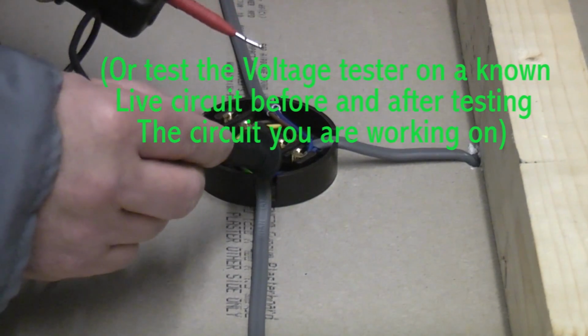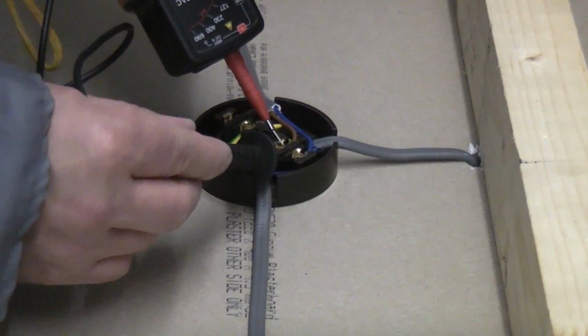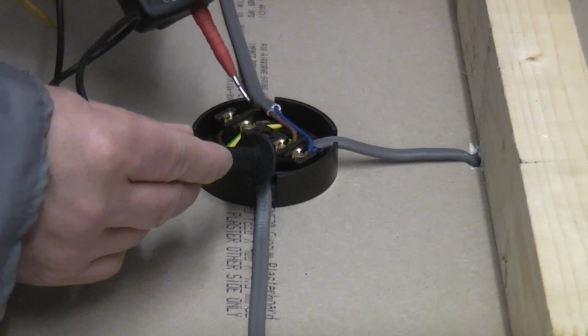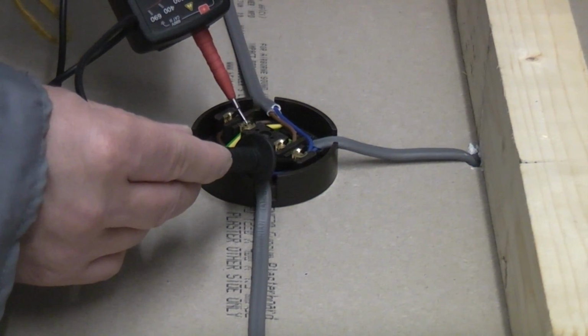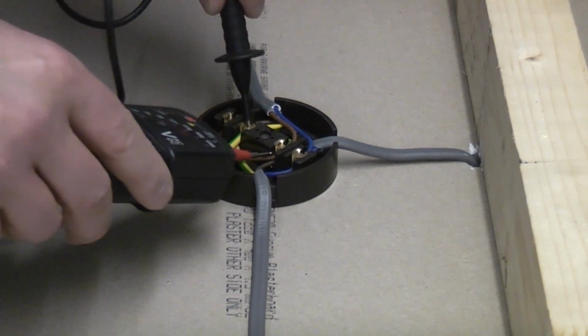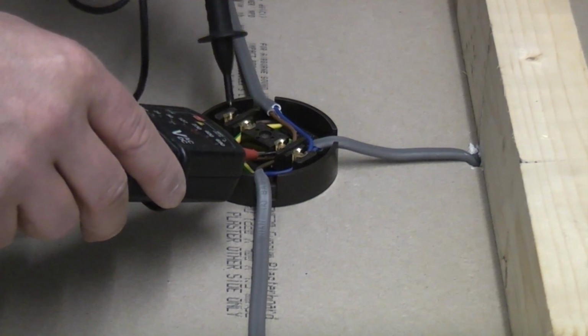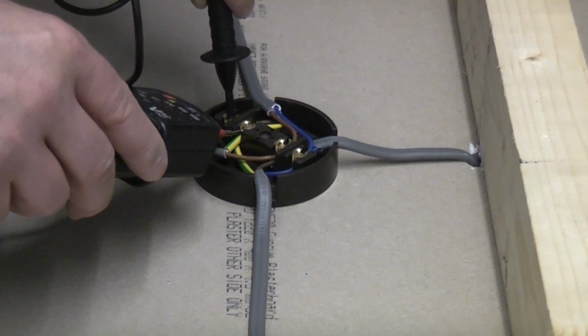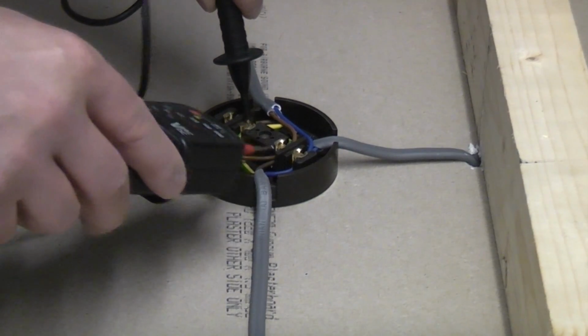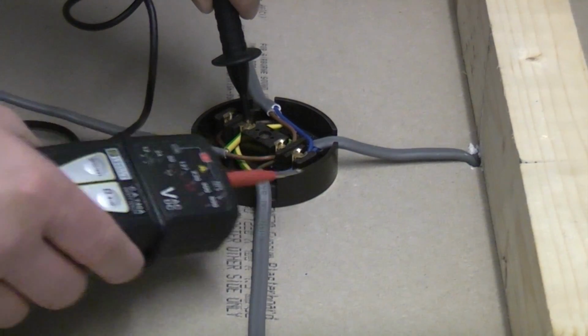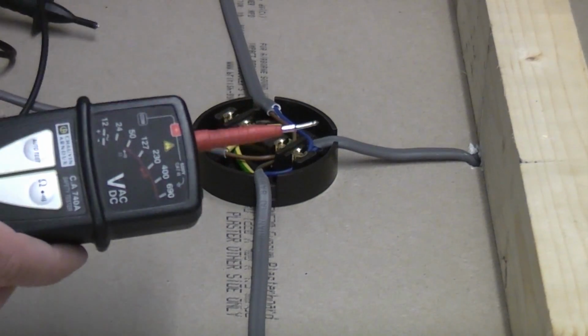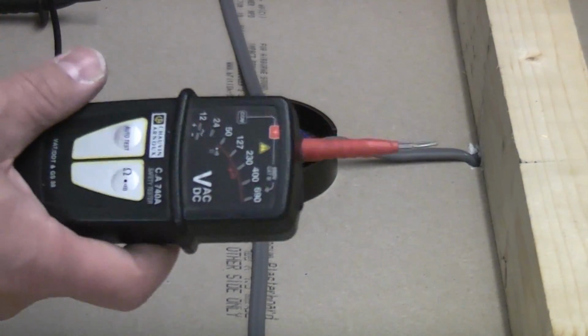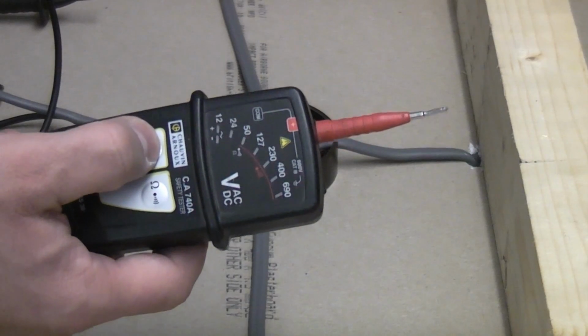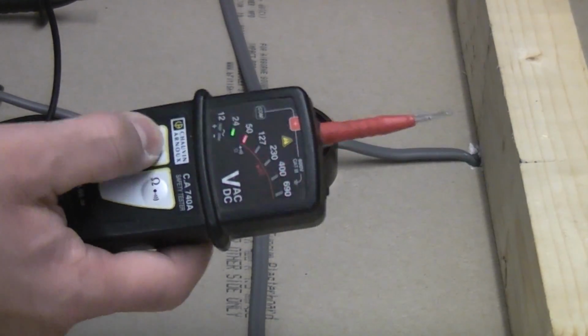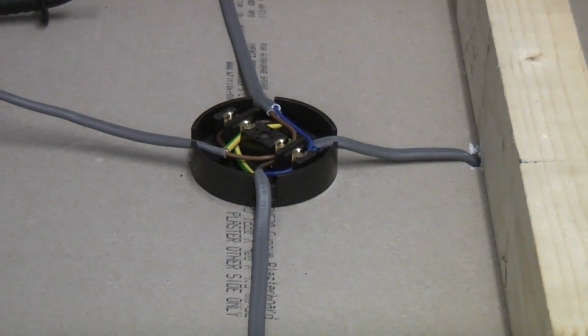We're now going to probe between neutral and live, which is dead, neutral and earth and live. And we'll also just check the switch live terminal. We can probe all of those terminals and the tester isn't lighting up at all, so it is completely dead. We are now safe to work on this circuit. Before we do, we need to check that the tester is still working, which it is. So we can now safely work on this circuit.